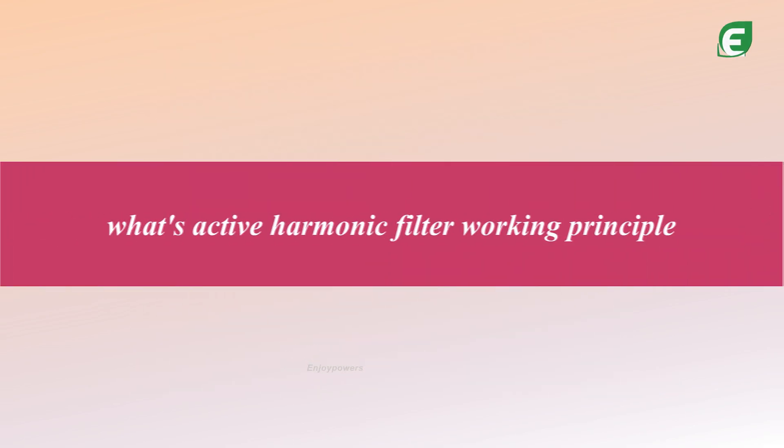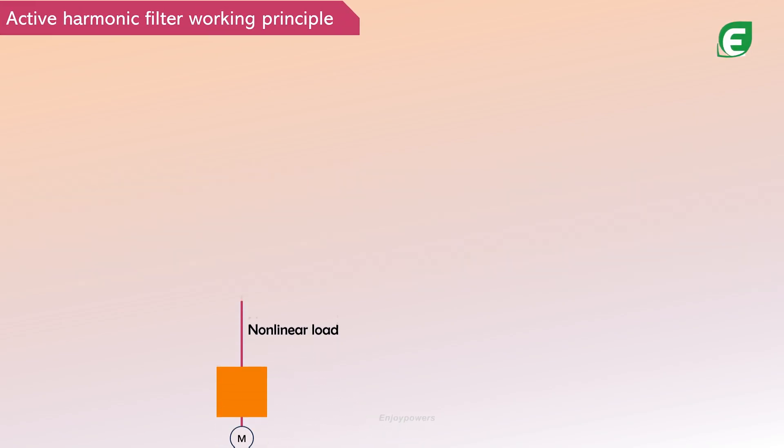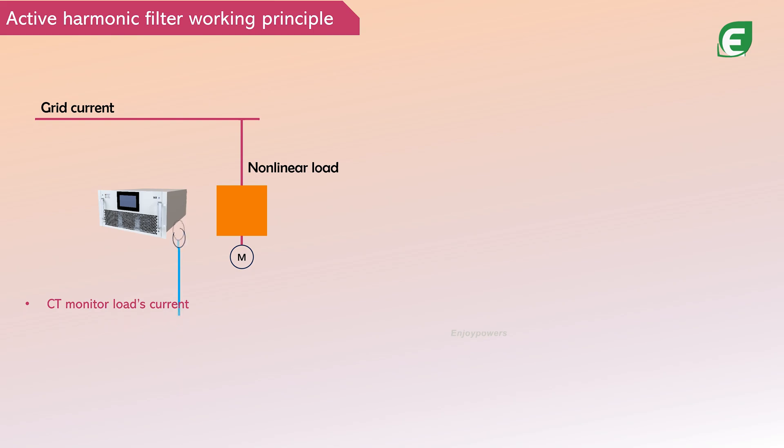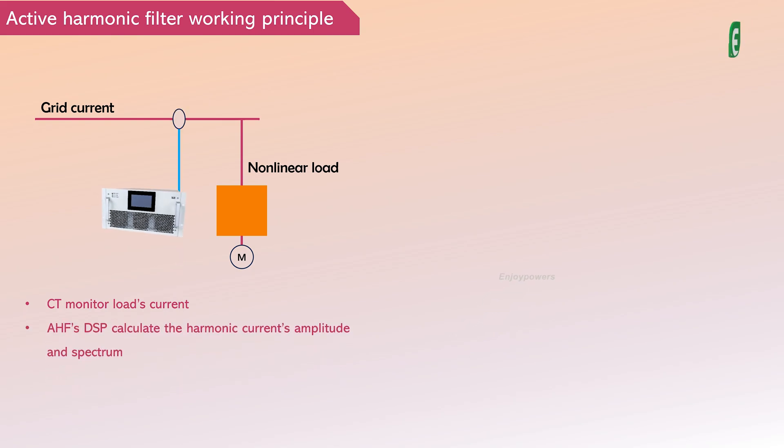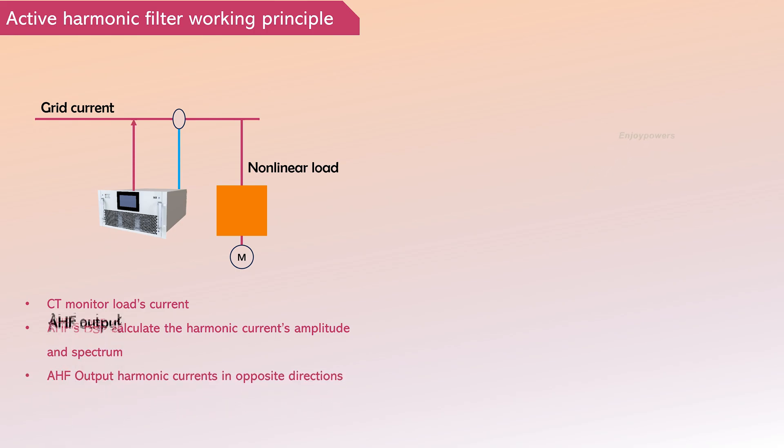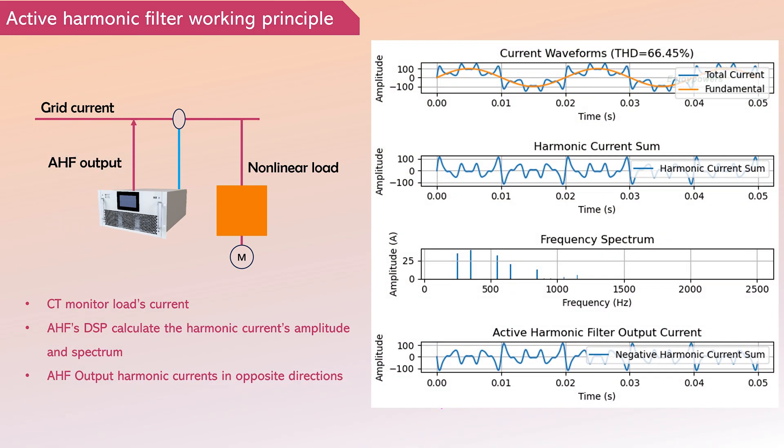What's active harmonic filter working principle? AHF collects current information from the load using current transformers. The AHF's DSP rapidly calculates the amplitude and spectrum of harmonics, controlling the AHF to output an opposing harmonic current, thereby achieving harmonic compensation.